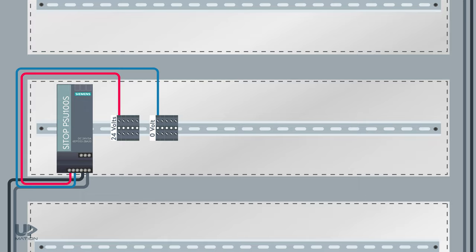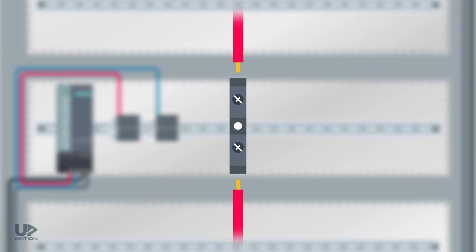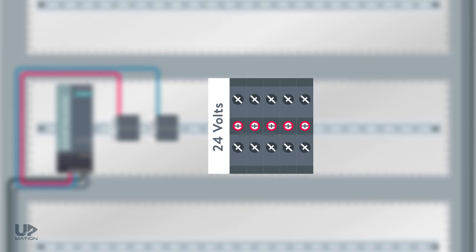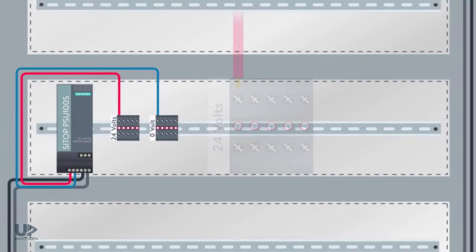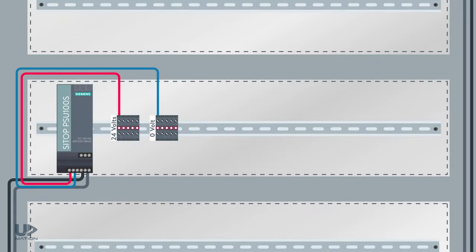As you may know from our previous videos, by using a terminal block you can join two wires to each other. To connect all of the terminal blocks of the same purpose, we can use a terminal strip jumper. I should put it in the middle holes of the terminal blocks and fasten its screws. In this way, all of these terminal blocks will have the same voltage of 24 volts. I have planned to dedicate this power supply to the PLC CPU and its input-output modules to protect them more against any faults that may happen outside of the control panel.